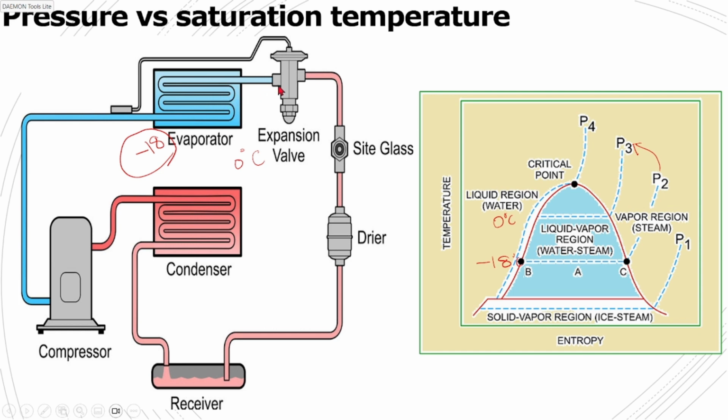What does it mean? Let's say in case of incorrect adjustment of the expansion valve, insufficient refrigerant enters the evaporator. What happens? Only at the halfway point of the evaporator, all the refrigerant will have evaporated, so the later part of the evaporator will not be useful. In the same way, if the expansion valve opens too much, then too much liquid will enter and some liquid particles will remain and exit the evaporator, because there won't be complete heat exchange as the flow is too much. There will be a chance that your compressor gets liquid, which causes damage to the compressor, right?